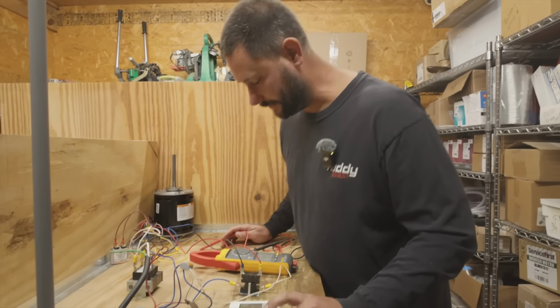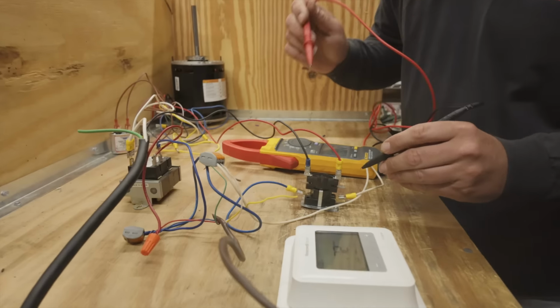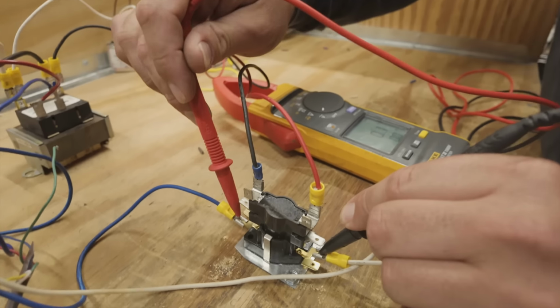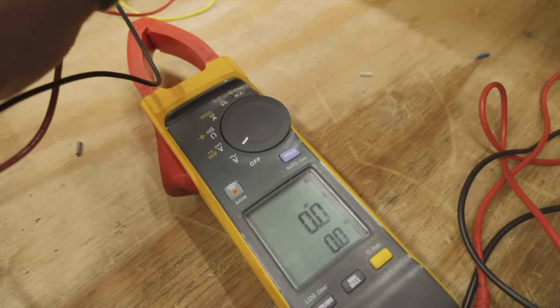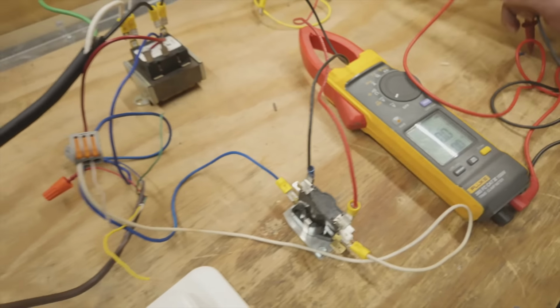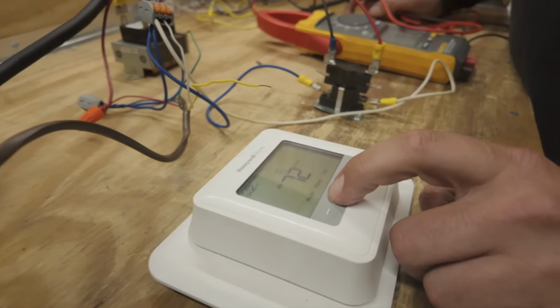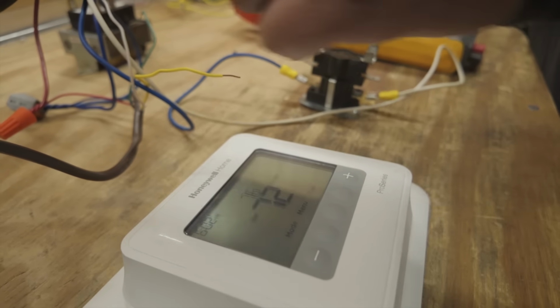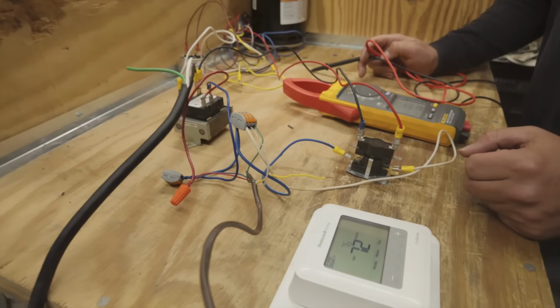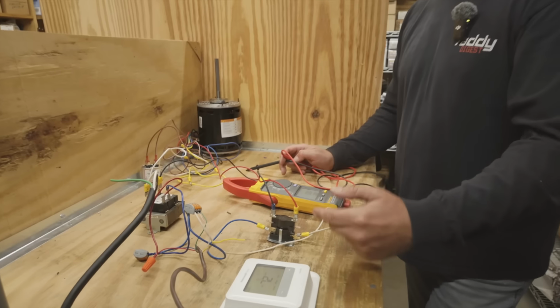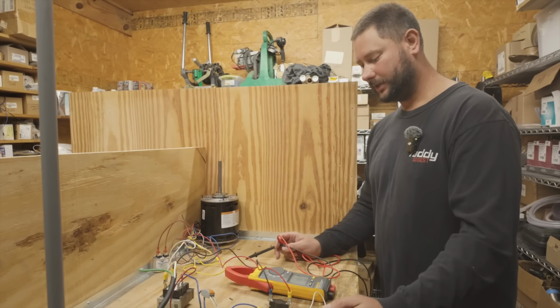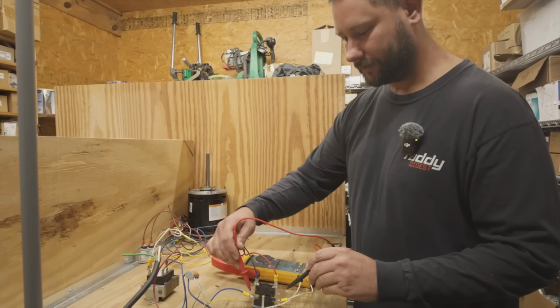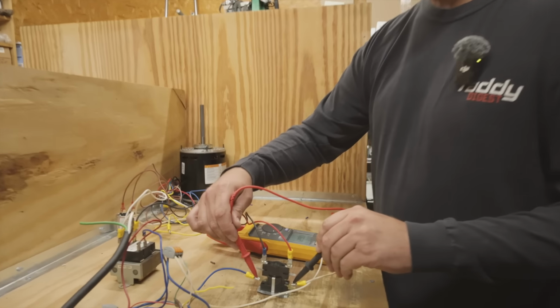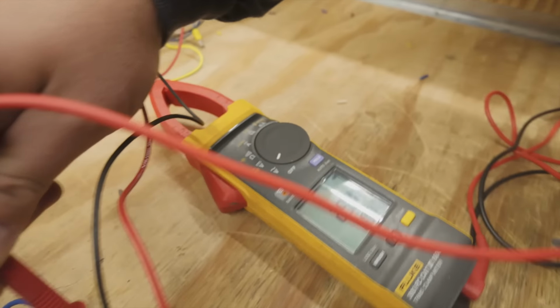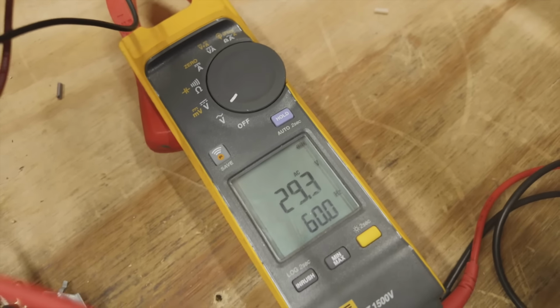Let's go ahead and turn, and just to verify, we don't have voltage at our coil. No voltage at our coil. Look at there. Turn mode to heat because we got our white wire connected. White and blue, C and W connected to our coil. It clicked. 29 volts. Look at that, 29 volts to our coil.